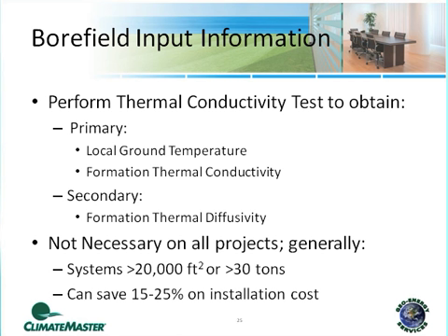Typically, I've seen low-end costs of $8,000 and high-end costs up to about $16,000. It's going to vary depending on where you're at. It's going to depend on how deep your test borehole is. It's going to vary on whether you require just standard bentonite grout or thermally enhanced grout on the test borehole, and if you're going to try to reuse that borehole, which you can, in the design of the project, then you're probably going to do it with thermally enhanced grout. All those types of things fluctuate the cost of the test itself.